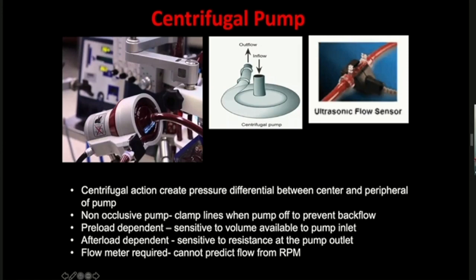This pump is very preload and afterload dependent — sensitive to the volume available at the pump inlet (preload dependent) and to any resistance at the pump outlet. Any obstruction or kinking can interrupt the pump and cause fluctuations in motor flow. Another characteristic of the centrifugal pump is that you cannot reliably predict how much flow you will achieve from a given RPM setting. Unlike a roller pump with a consistent linear relationship, for a centrifugal pump you need to titrate the RPM at the bedside and observe the resulting flow.